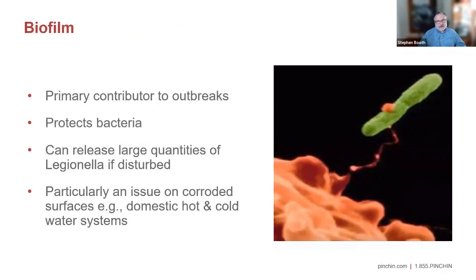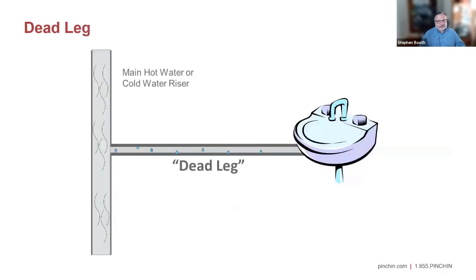The other thing that can have an influence on Legionella in your buildings is biofilm—the bacteria and gunk that grows on the wall of a cooling tower sump or inside a corroded pipe. That biofilm can actually protect the Legionella and other bacteria from the disinfectants we use, whether that's chlorine in the potable water system or treatment chemicals in the cooling tower. It acts as a barrier, and the bacteria can hide out in the biofilm without being impacted. When there are shutdowns, the draining and refilling of the system can dislodge the biofilm and result in really high concentrations.